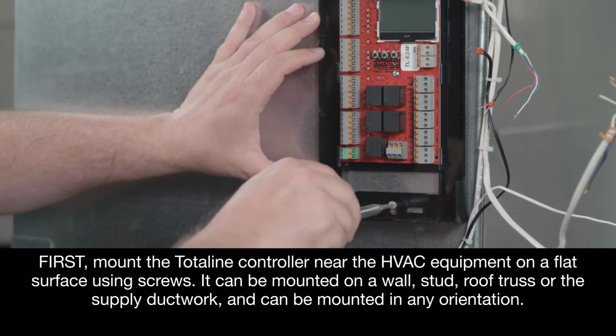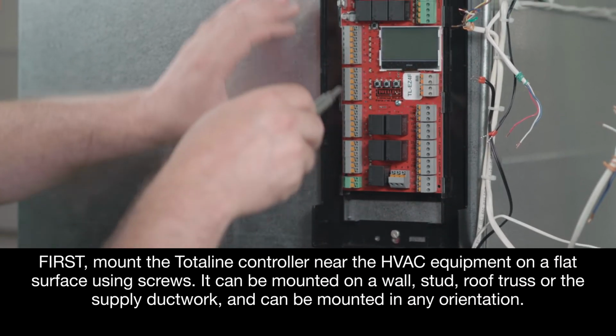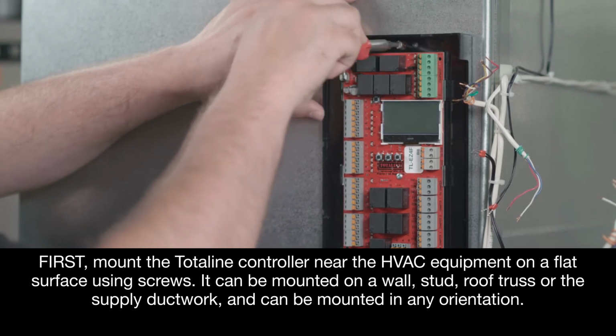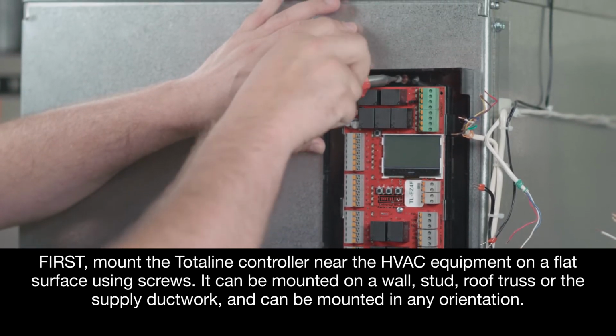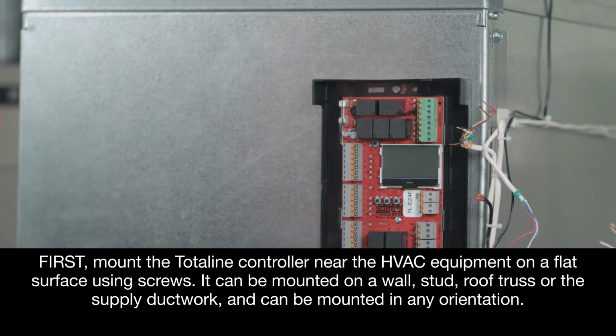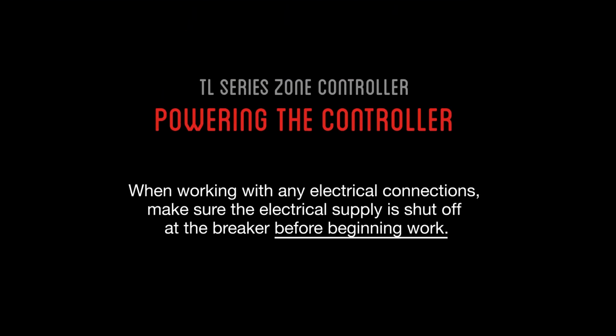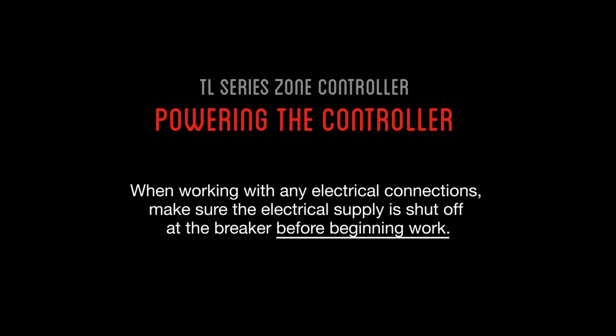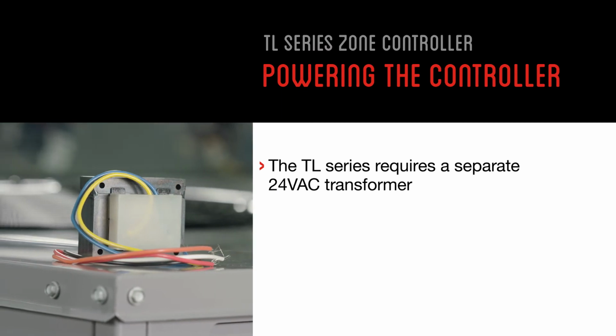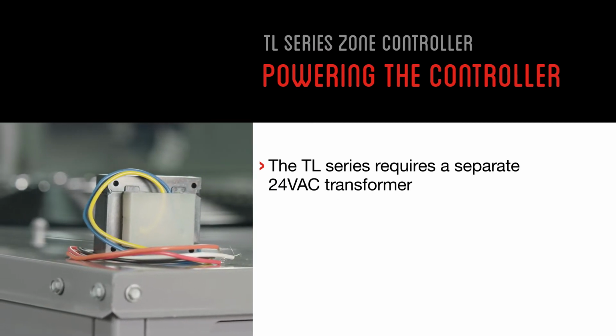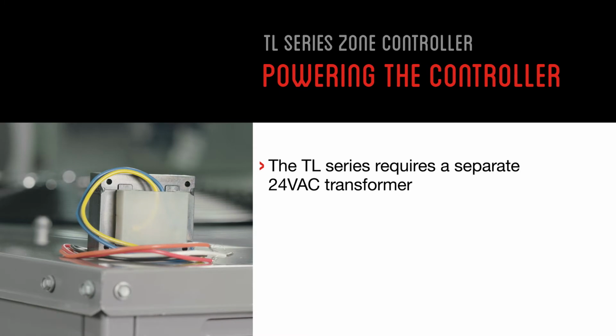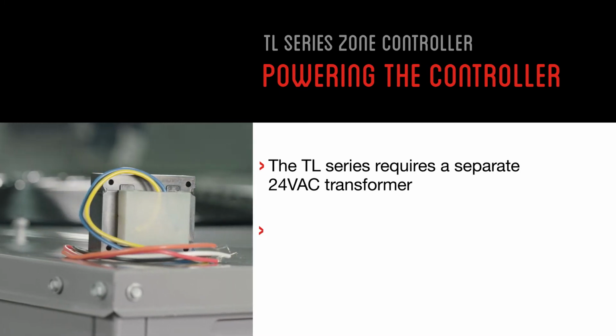First, mount the Totaline controller near the HVAC equipment on a flat surface using screws. It can be mounted on a wall, stud, roof truss, or the supply ductwork, and can be mounted in any orientation. When working with any electrical connections, please make sure the electrical supply is shut off at the breaker before beginning work. Be aware that the TL series system requires a separate 24-volt AC transformer, which is not included, for powering the TL series controller, zone thermostats, and dampers.